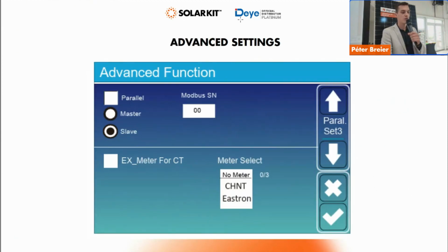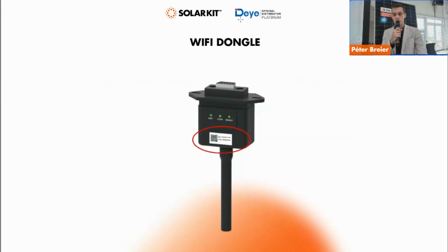In the advanced function, there is a parallel setting which could be important, but as I mentioned, please have a short conversation with us before you want to install a parallel system with Deye, just to make sure everything is fine and you are well prepared for the installation. And there is an option for the meter. So if you want to use an external meter instead of the original CTs, you have to mark that setting, and you have to choose which kind of meter you are using, the Chint or the Eastron. If you don't change that and you have a meter connected, it will not measure anything at that point.